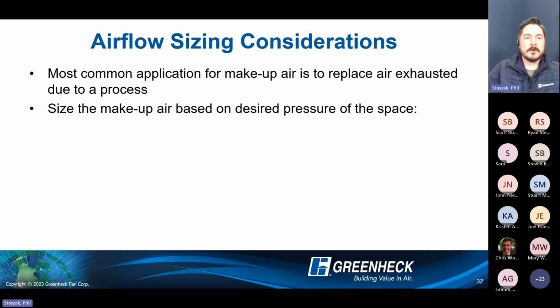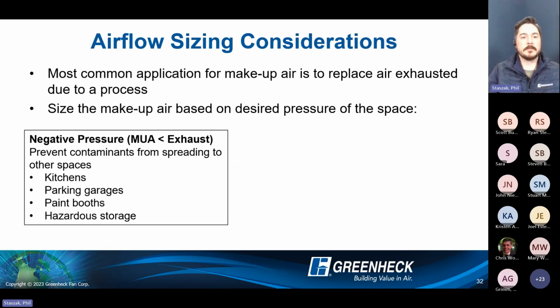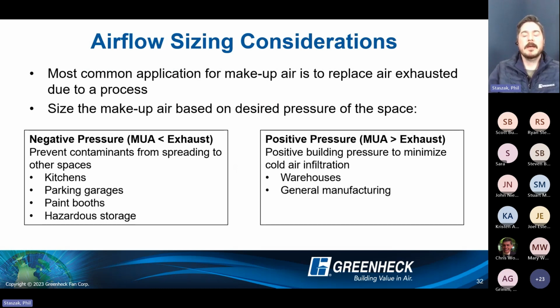Okay, so airflow considerations. In most applications, as I explained earlier, it's more of a 1-for-1. We're exhausting X CFM, therefore we need to bring in X CFM to roughly balance out that airflow. Slight negative, slight positive in some cases. Where you want a slight negative: kitchens, parking garages, paint booths, hazardous storage, wastewater treatment plants, things like that.